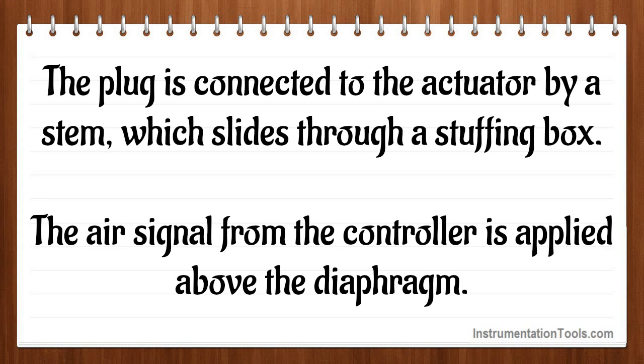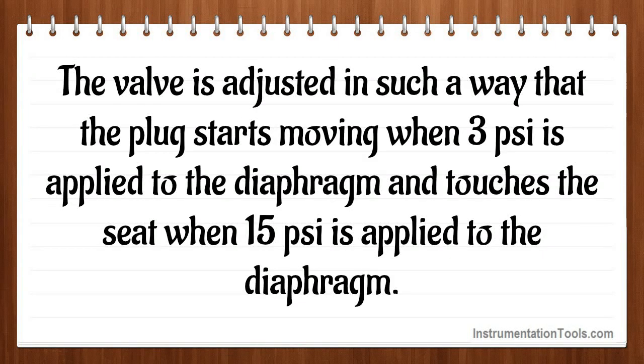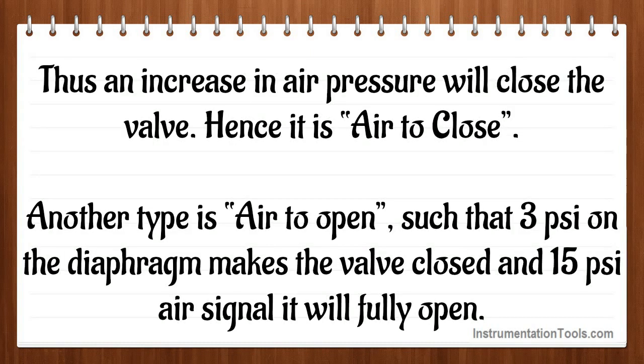The air signal from the controller is applied above the diaphragm. An increasing air signal will push the operator stem downwards against a force exerted by the spring on the diaphragm plate. The valve is adjusted such that the plug starts moving when 3 psi is applied to the diaphragm and touches the seat when 15 psi is applied. Thus an increase in air pressure will close the valve — hence it is air-to-close. Another type is air-to-open, such that 3 psi on the diaphragm makes the valve closed and 15 psi air signal will fully open it.